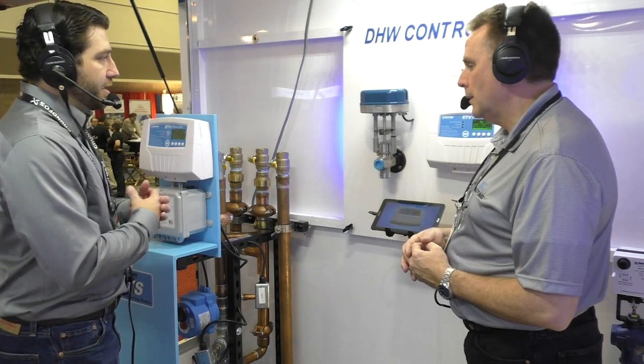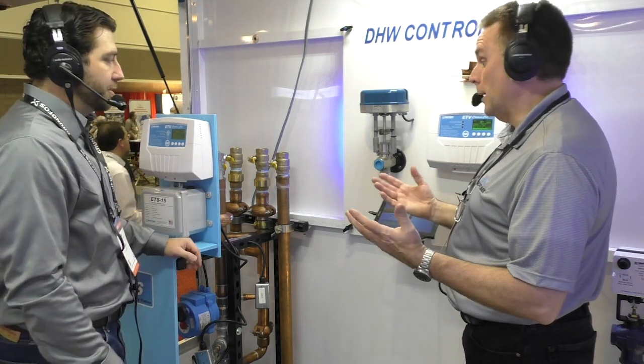And yeah, we really love this system, have great success with it. You know, love that it's more of a controls approach to this system, a control system, not necessarily a mechanical valve that is reacting to the changes. You've got a very simple 3-way control valve with the actuator and a great controls package in there that you can actually make your adjustments on, see the system feedback, and get that feed forward control, looking at that return water inlet temperature to see if you're going to have that change in demand. So really have enjoyed having this system and being able to provide it to our customers. I'm glad to hear that.